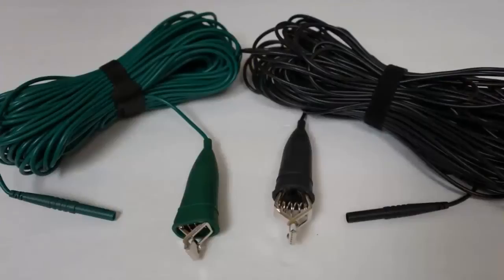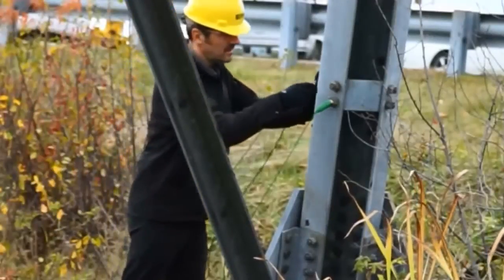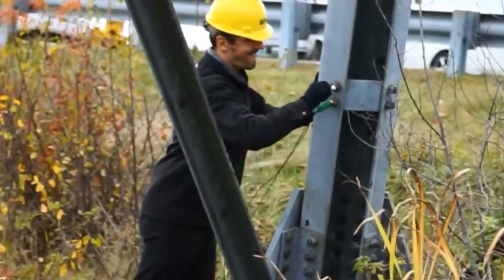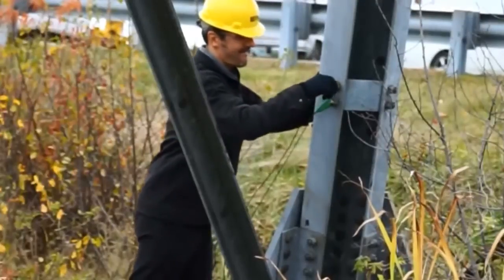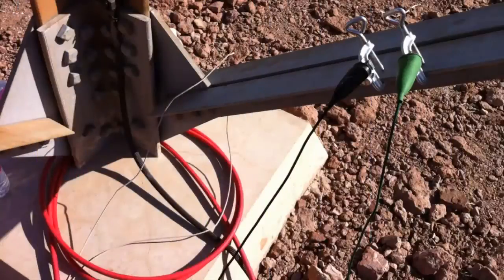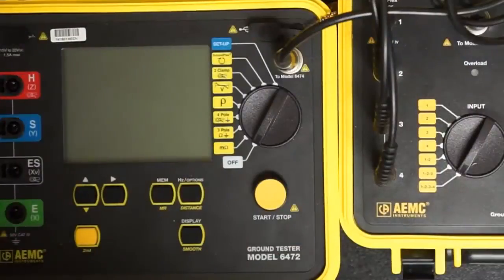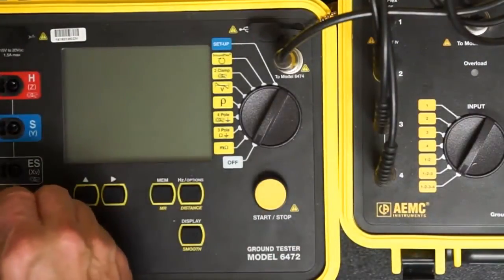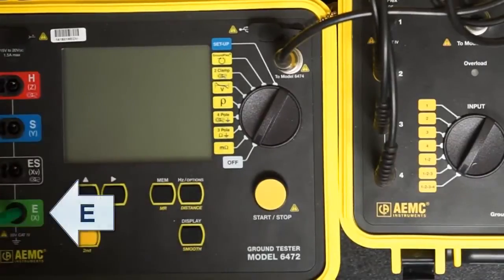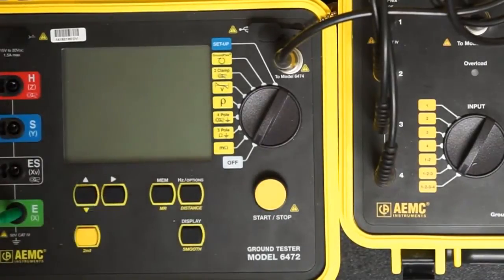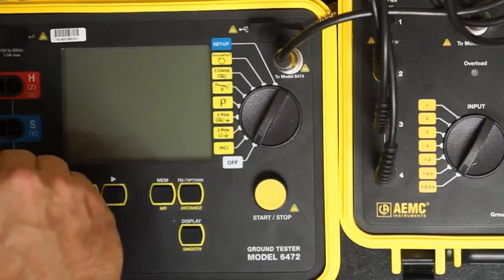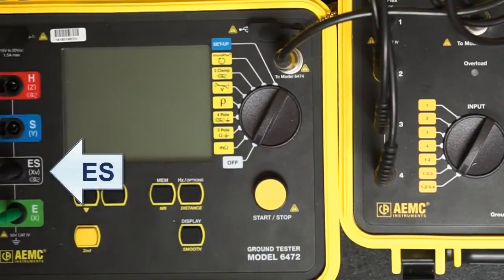Locate the green and black test leads. The green lead is used to inject current into our test setup. The black lead is used for voltage measurement. Both leads must be attached to a tower leg next to each other at a point higher than the GroundFlex sensor. This can be any leg as long as both probes are connected to the same leg. Connect the green lead to the Model 6472 instrument by inserting it into the connector labeled E. Insert the black lead into the connector labeled ES.